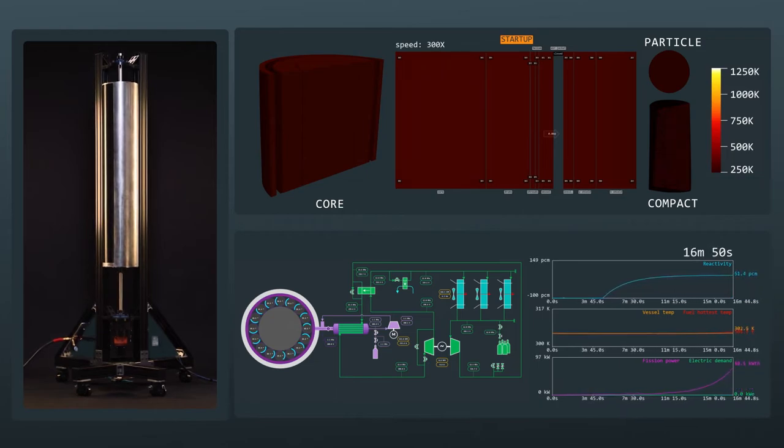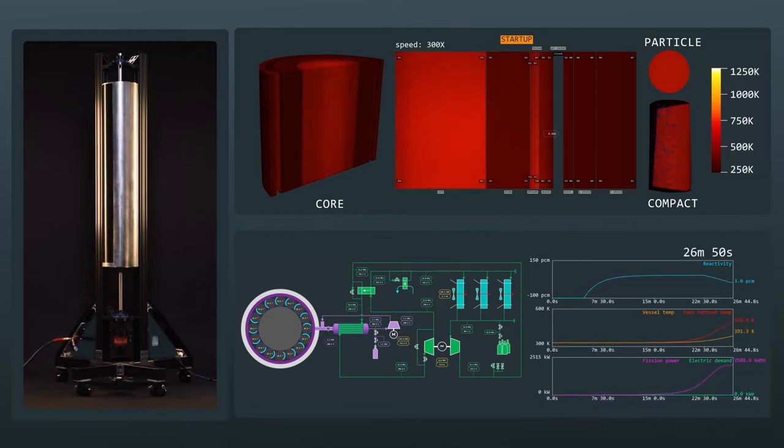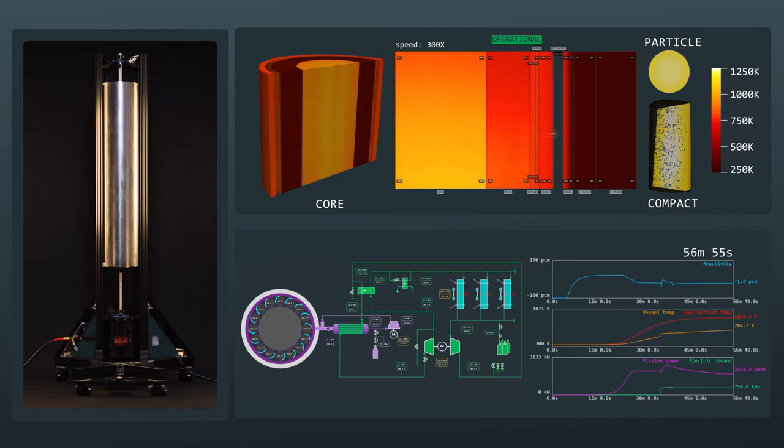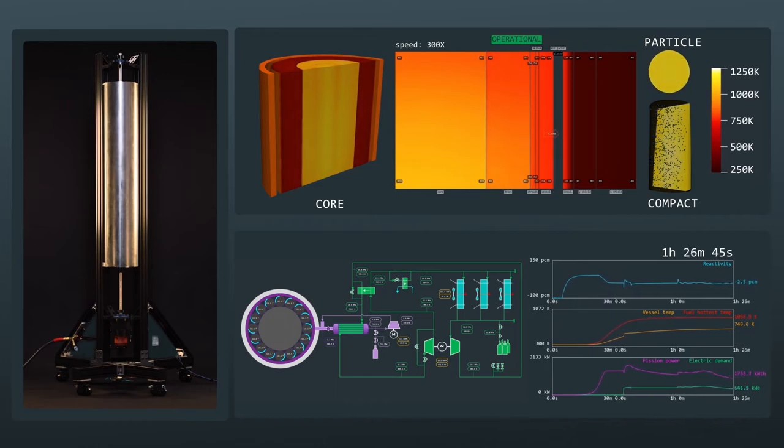the control system further turns the drums in order to maintain criticality. The drums move by an additional 30 degrees to offset the core's negative temperature feedback coefficient. The turbo machinery ramps up to speed as the core reaches target temperature, and a circuit breaker connects the microgrid electrical load.